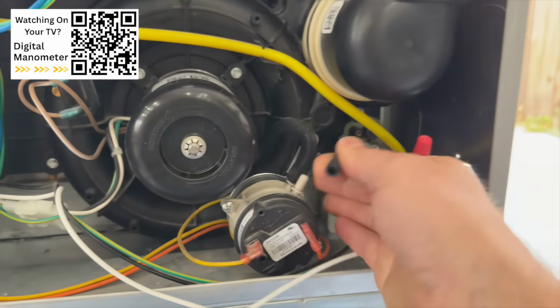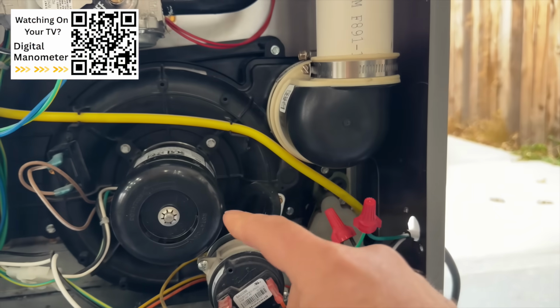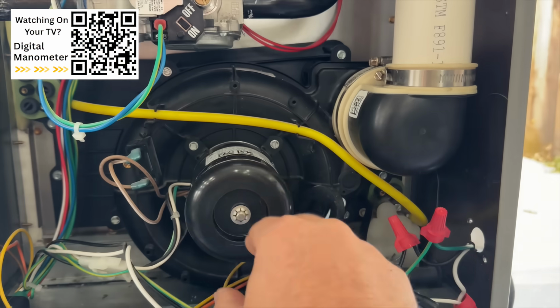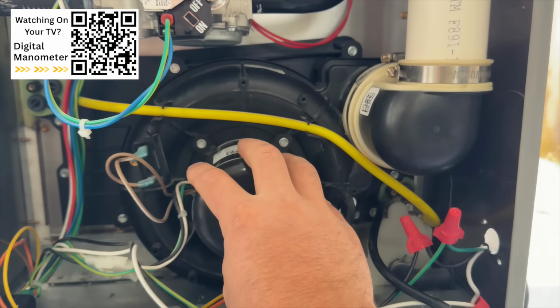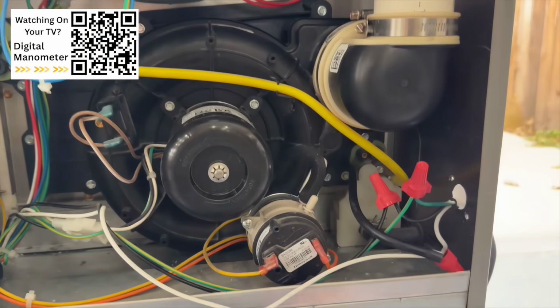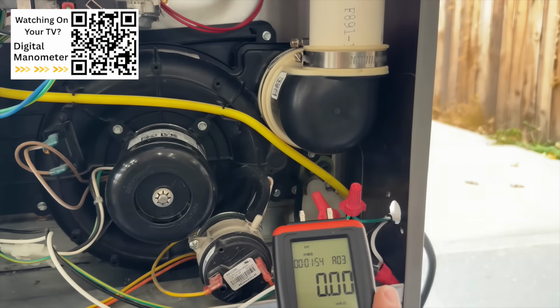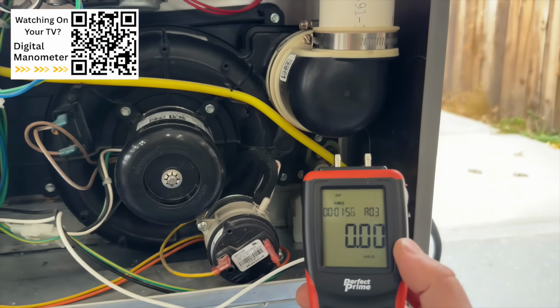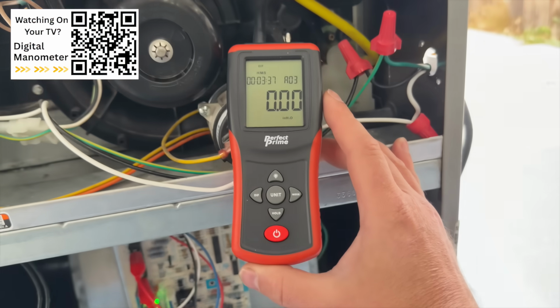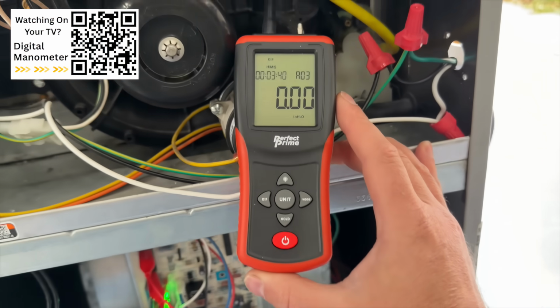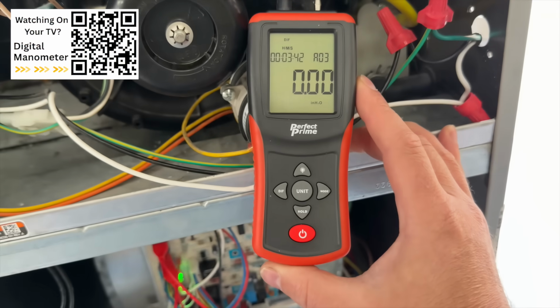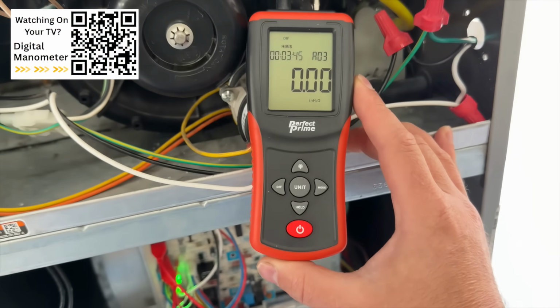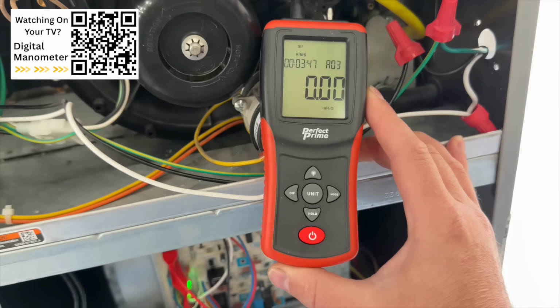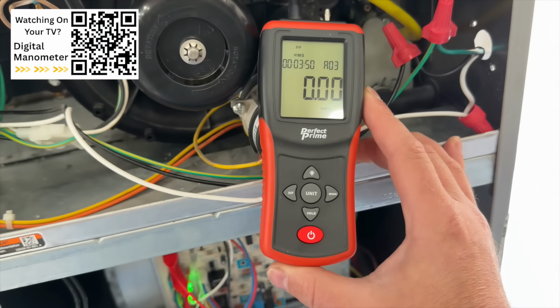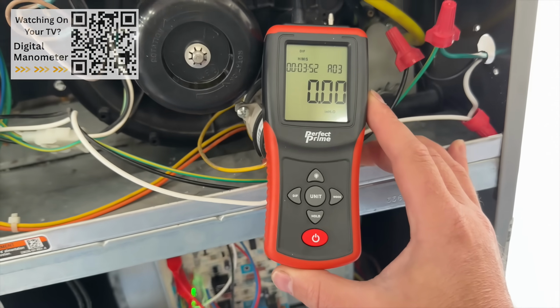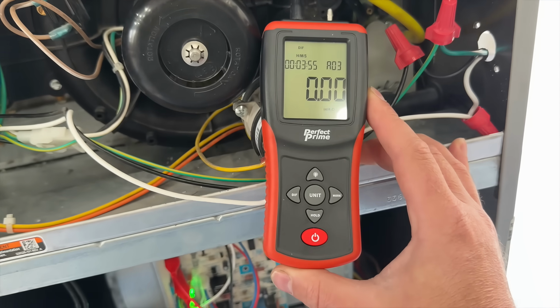So what we're going to do is take off this hose that goes to the collector box here. That should only have pressure when this is spinning. If this is not spinning, you should not have any pressure here. And we're going to connect our manometer here and then turn our blower on and see if this has any movement. All right, guys, so we've got our blower motor turned on. We have this connected to our manometer. And as you can see, we have zero. Nothing is reading on here. So once we create a hole in the heat exchanger, this number should change once we turn the blower motor on again and redo this test.